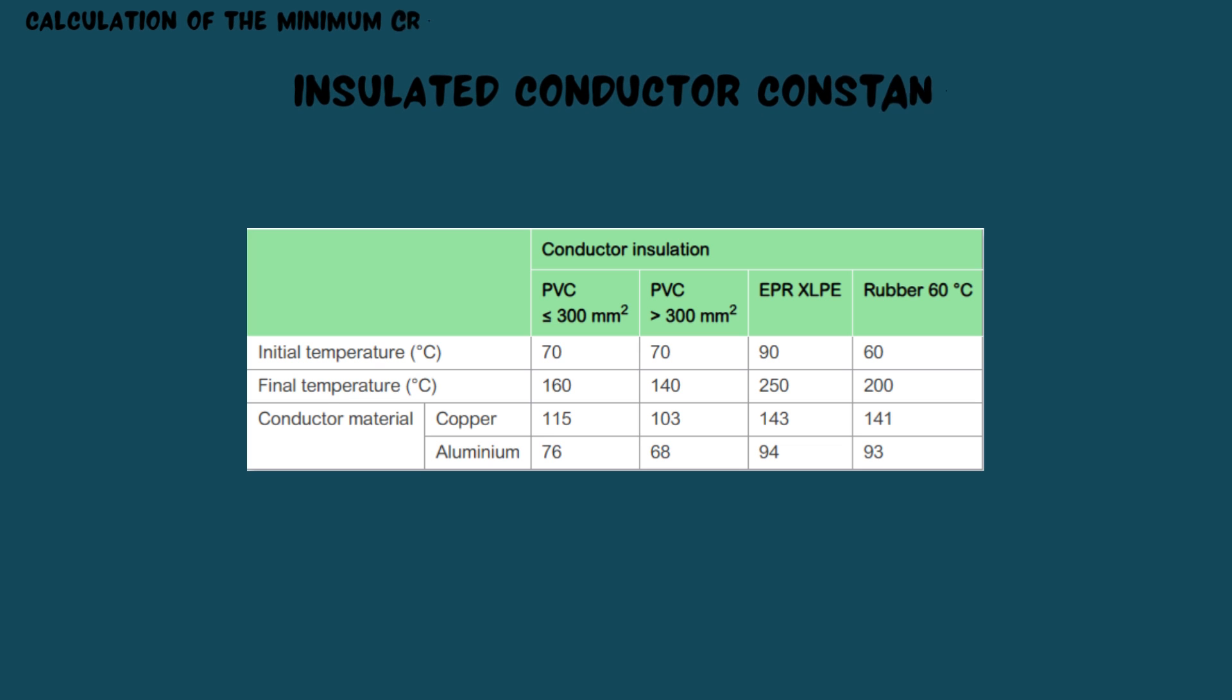The factor K is dependent on the cable insulation, allowable temperature rise under fault conditions, conductor resistivity, and heat capacity. Typical values of K are shown in the table.